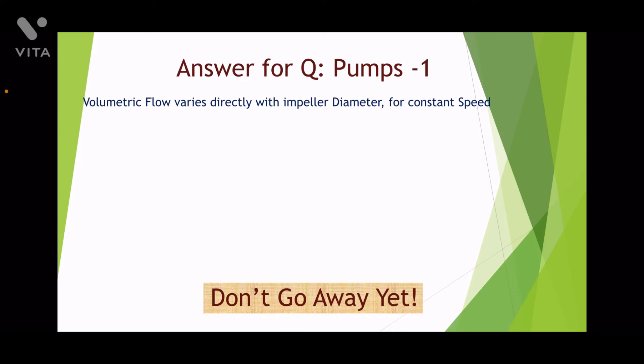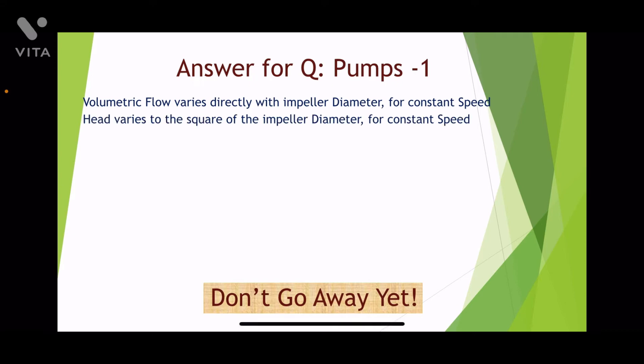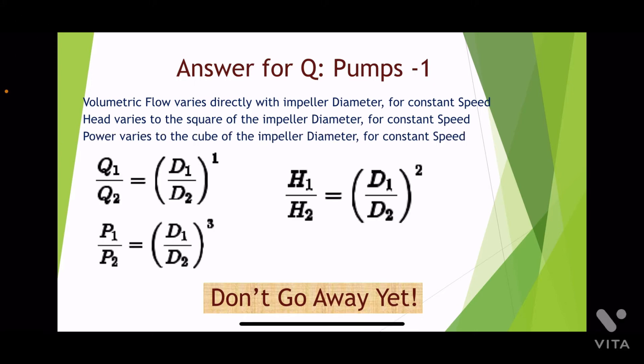The pump affinity law states that the volumetric flow varies directly with the impeller diameter for constant speed. The developed head varies to the square of the impeller diameter for constant speed. The power required varies to the cube of the impeller diameter for constant speed.